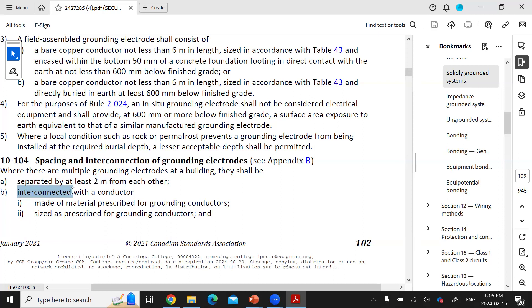This interconnection offers that low impedance path for any of the fault current and enables the quick operation of those overcurrent protection devices. So this item B is going to make sure that the interconnection of those grounding electrodes are going to extend the equipotential.